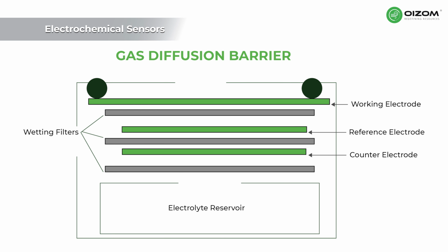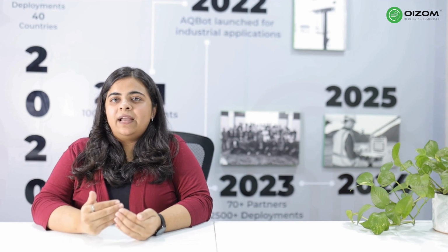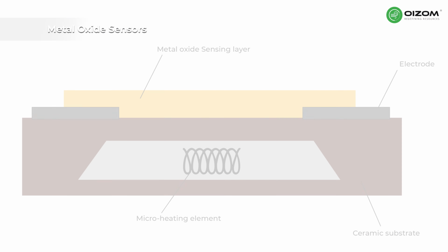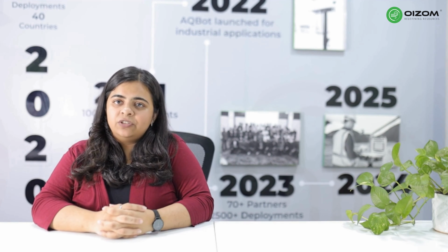3. Electrochemical sensors. These are small, affordable sensors where NO and NO2 create a tiny electric signal when they react inside the sensor. The signal strength shows how much gas is in the air, which is great for real-time ambient monitoring. 4. Metal oxide sensors. Heated to high temperatures, these sensors detect NOx based on how the gas changes their conductivity. They're simple and useful for continuous detection.